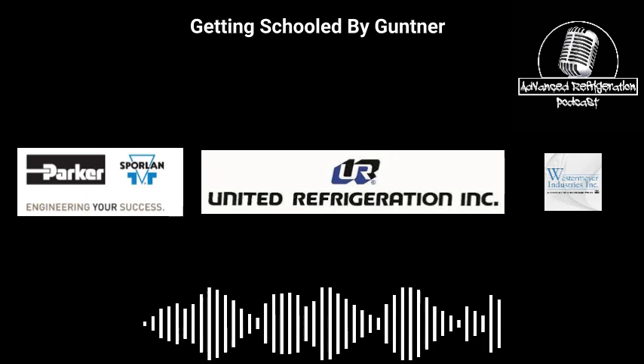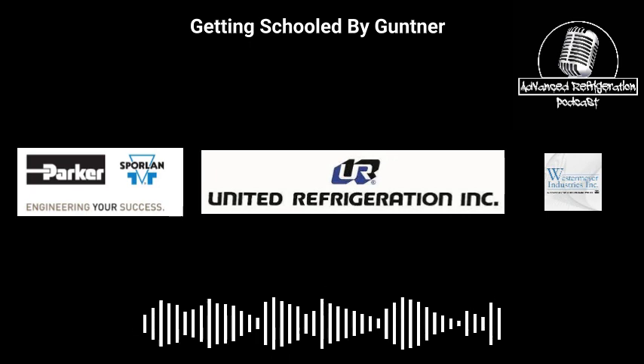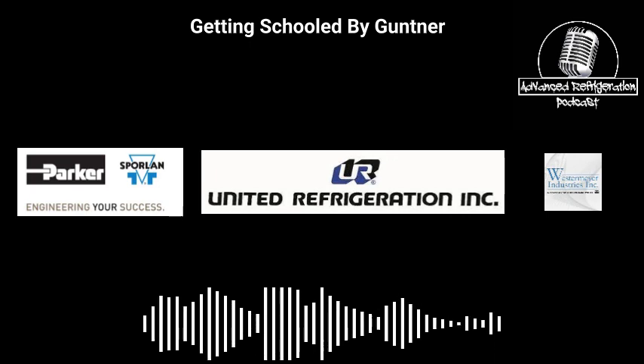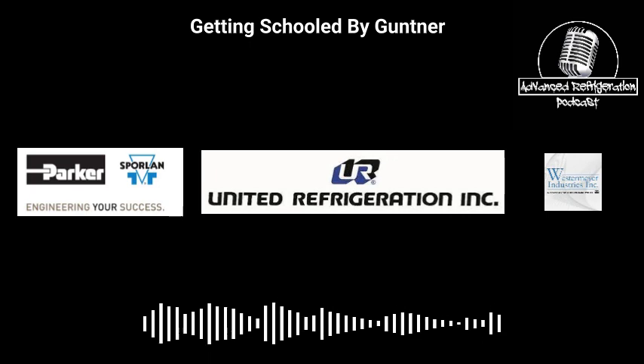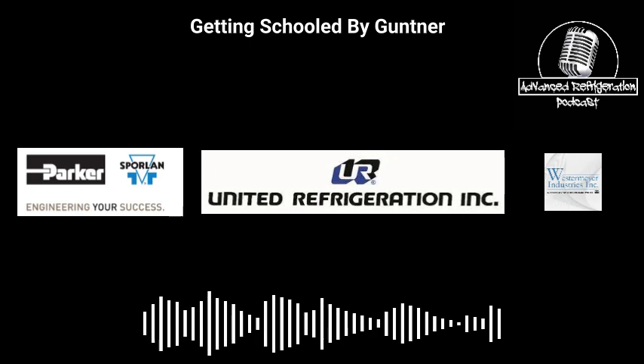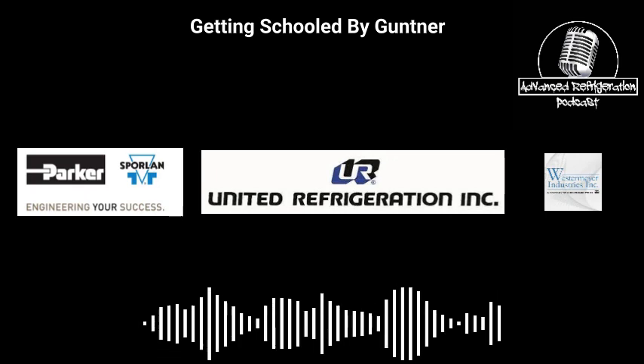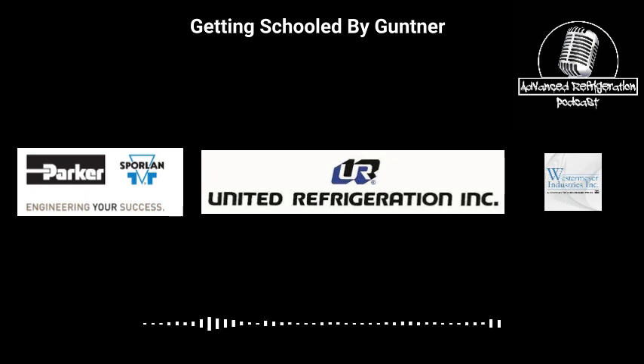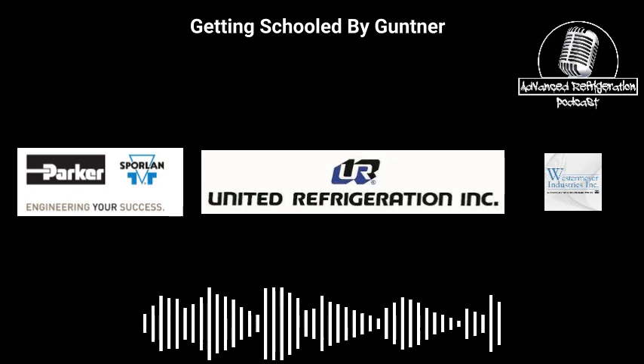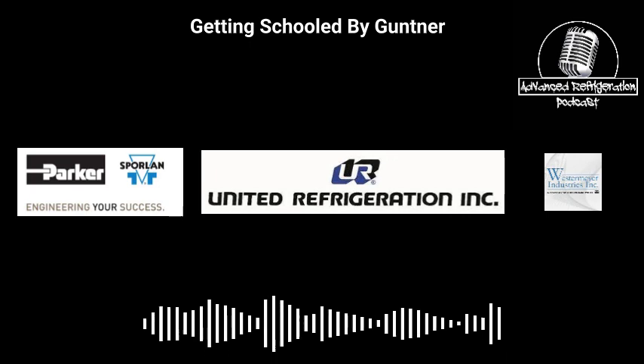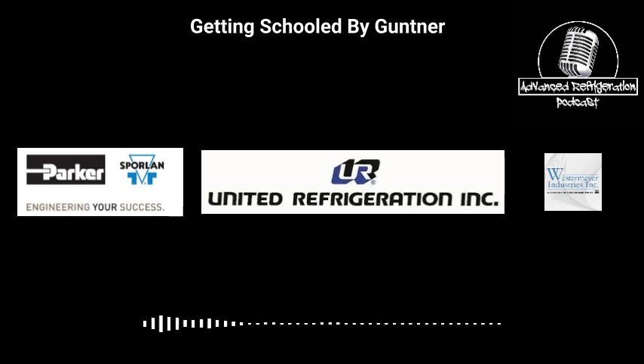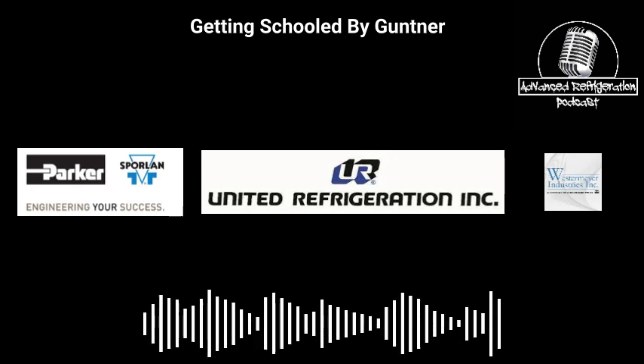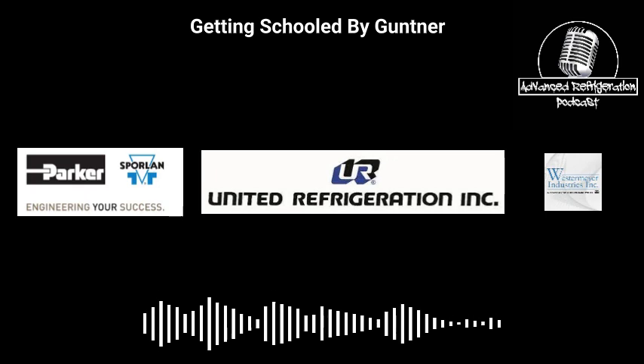Our previous controller, the GMM EC, that's our legacy controller. That one, you needed an inverter if you wanted 10 to 0. With our newest controller, it's baked in. So it's just a setting on the controller. That's another call I get sometimes where it's been set up, but the signal's not inverted. That's an easy fix. It's just going into the settings and inverting the signal.